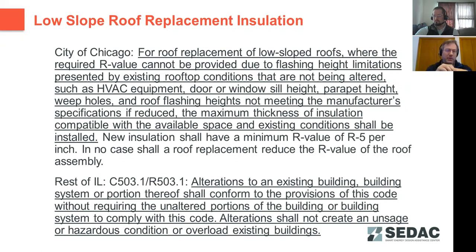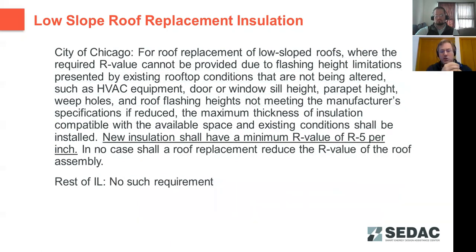So the only piece on the next slide here that City of Chicago calls out that is not required by the IECC is that City of Chicago states that the insulation must have a minimum of R5 per inch. So it's nice that the City of Chicago has this amendment that spells it out. However, the IECC does have provisions that effectively provide the same benefit for the rest of the state of Illinois. So regardless of where you are in the state of Illinois, the real objective here is you have to do the best you can within the existing constraints that you have.